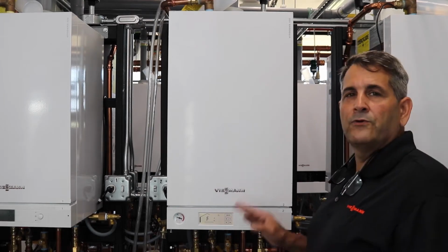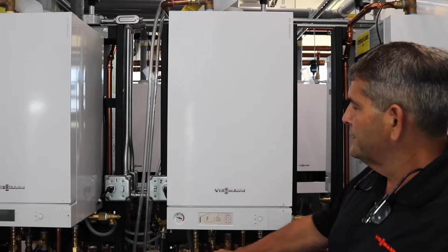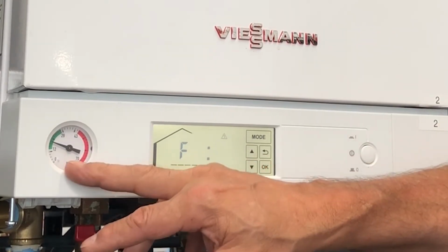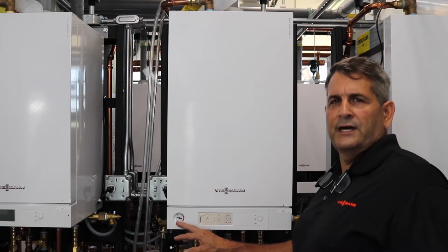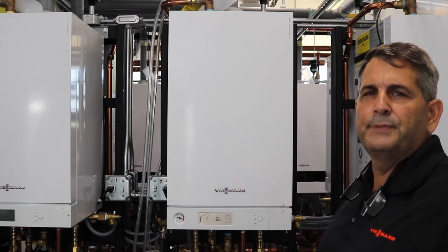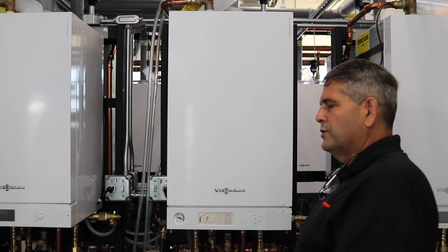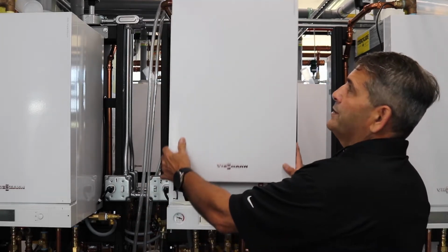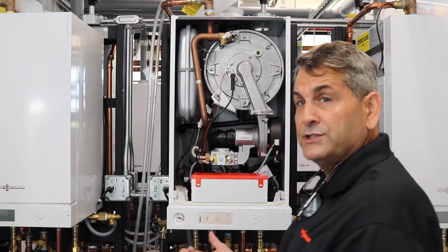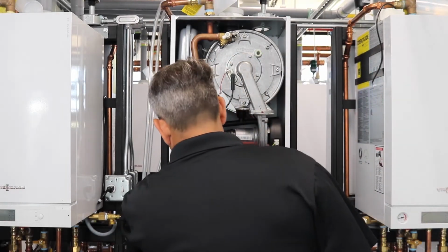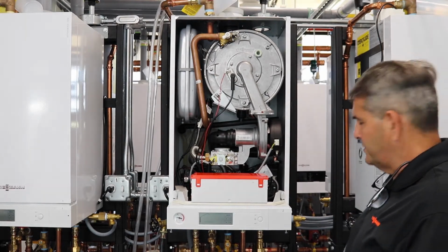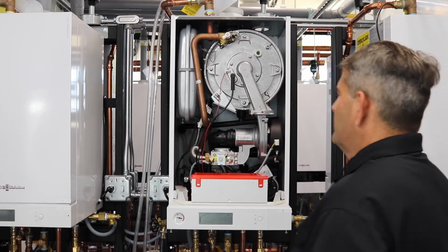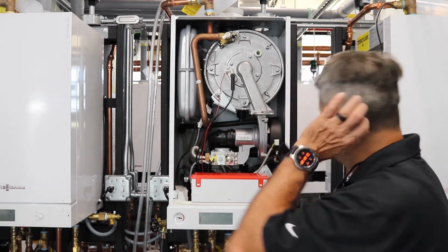Remember, we're going to power the boiler off, and the things that we want to check is our water pressure in the green. As we can see, the water pressure is in the green, which means we're above the 12 psi that you need to be activated on this boiler. Remember, you have to remove the 2 screws on the very bottom to take the cover off, and then we're going to lift the cover off the top. Now we're going to shut the power off, and we'll make sure our boiler is isolated from the system side. And then we're going to start taking a look at what could cause it.